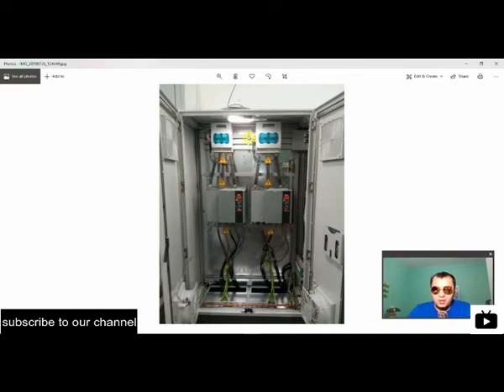Another big issue on this project was heat dissipation inside the cabinets, especially in this one, since these two soft starters from Danfoss, for the nominal current they can deliver, shouldn't be operating at more than 40 degrees Celsius. So we had to make sure that the temperature inside this cabinet doesn't go over 40 degrees Celsius. And since we commissioned this system in the summer, so the worst possible scenario, we also immediately got the proof that our climate control system for this cabinet is working properly, so it's properly dimensioned.